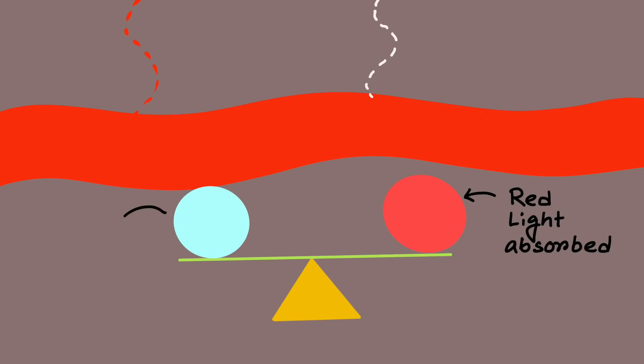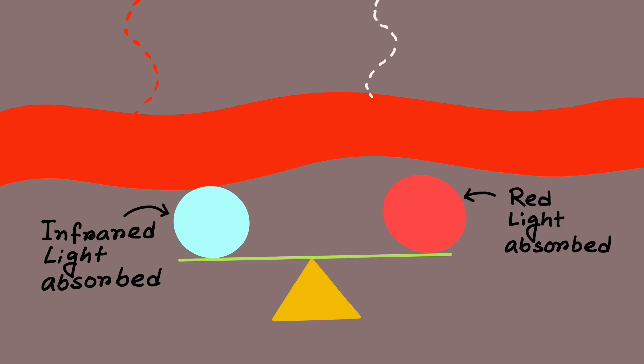The pulse oximeter works out the oxygen saturation by comparing how much red light and infrared light is absorbed by the blood. Depending on the amounts of oxyhemoglobin and deoxyhemoglobin present, the ratio of the amount of red light absorbed compared to the amount of infrared light absorbed changes.